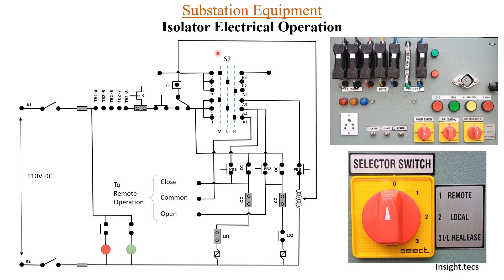If selector switch position 1 is selected, the contact of 1 will be closed and remote operation will be possible. If the selector switch is pointing at 2, that is for local operation. If we want to do the IL release, position 3 has to be selected. Once the key is inserted, we will be able to carry out local electrical operation.